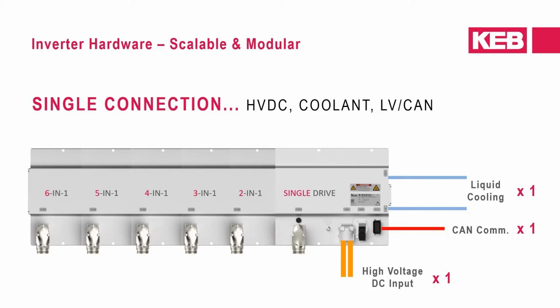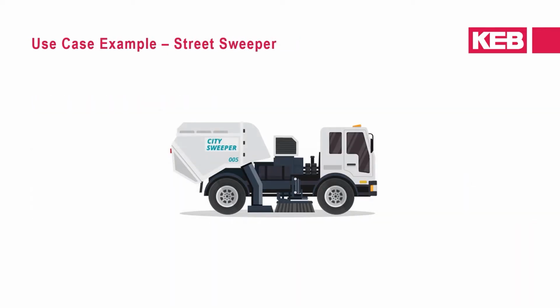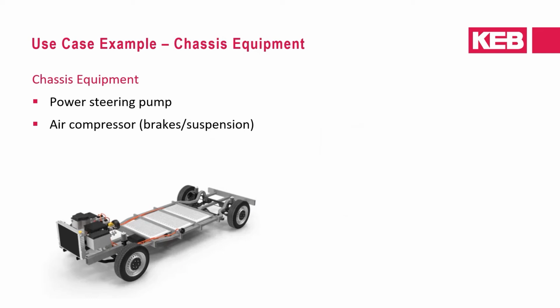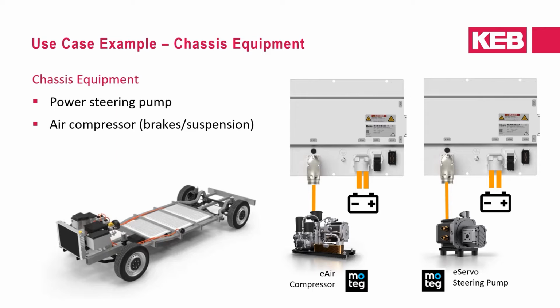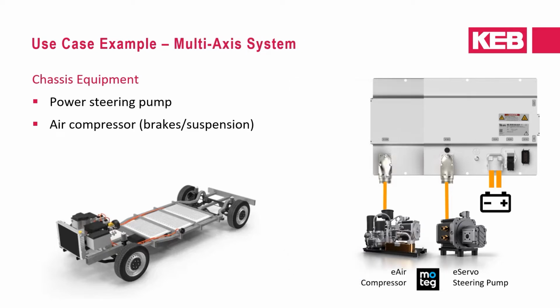And from a system standpoint, there's a single high voltage DC supply connection, single coolant circuit, and single low voltage connection, which also includes the CAN bus. To put this concept into context, let's look at a use case example, in this case, a street sweeper. The starting point for many applications is the chassis, so let's start there. The chassis would typically include a power steering pump and an air compressor for brakes, for example, 4 kilowatt each. Each can be electrified with its own inverter, or each could be electrified individually, but with a multi-axis system.